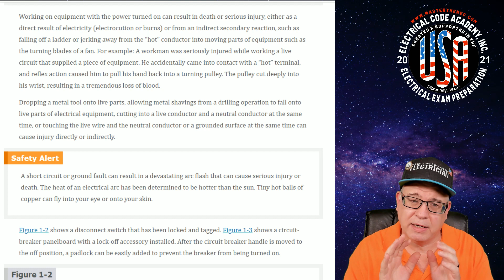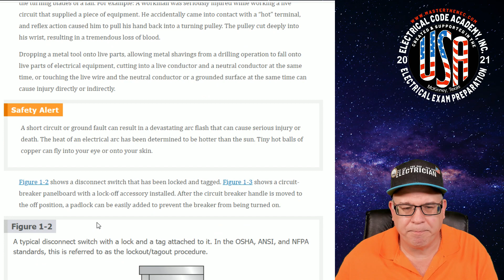Let's look at disconnecting means, since that plays a very important role in safety. Figure 1-2 in your program shows a disconnect switch that's been locked and tagged, locked in the open position. This would be used as part of a lockout tagout procedure — maybe the disconnect was required for a specific piece of equipment, or something wasn't within sight but required a disconnecting means. Section 110.25, which we'll learn about, gives the ability to lock something in the open position, and that's what was done here as part of the lockout tagout procedure.